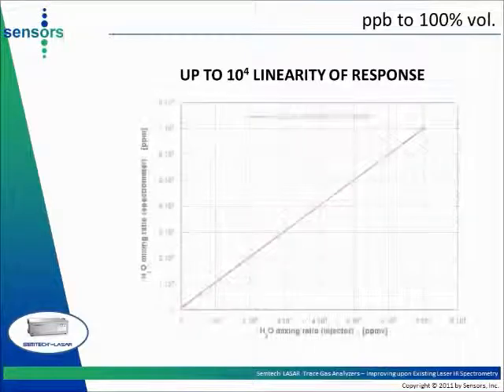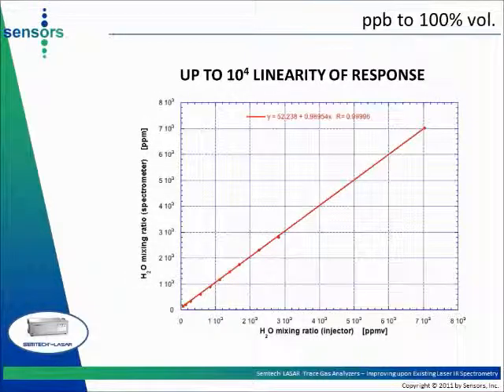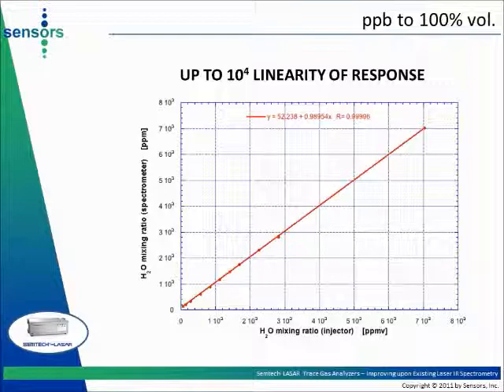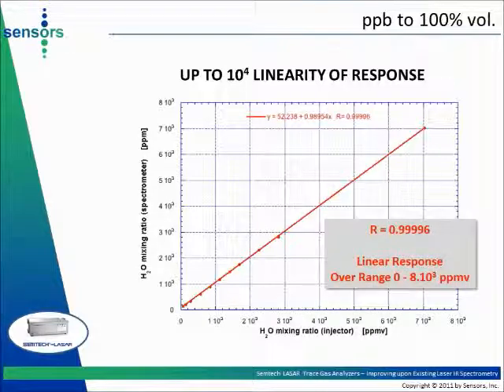The Semtech LASAR offers wide dynamic range response. In this experiment, the analyzer was calibrated for the measurement of water vapor from one parts per million to one percent volume. Validation results were obtained over the one to eight thousand parts per million range. Linearity of instrumental response over that range was characterized by a determination coefficient R of 0.99996.